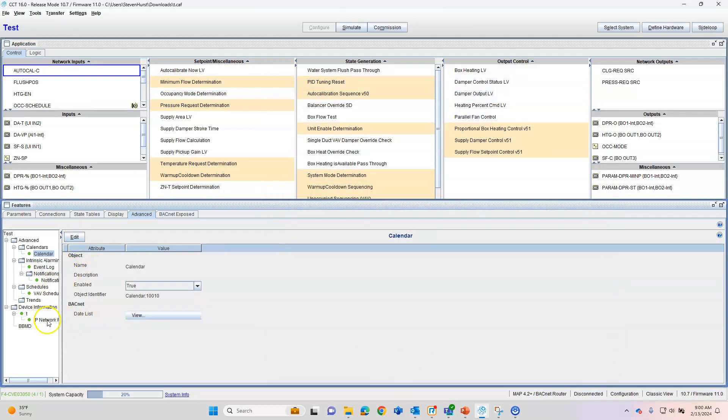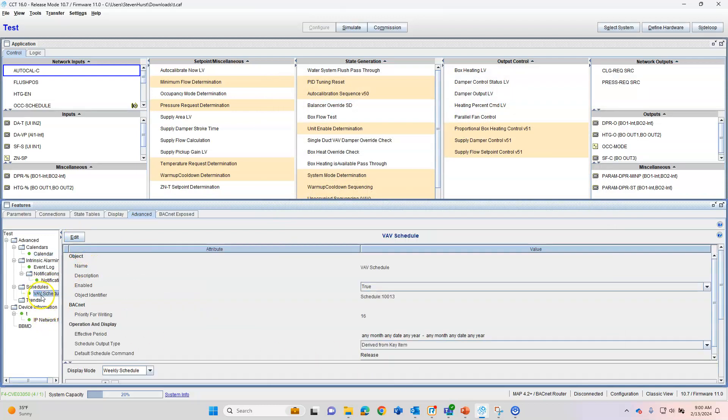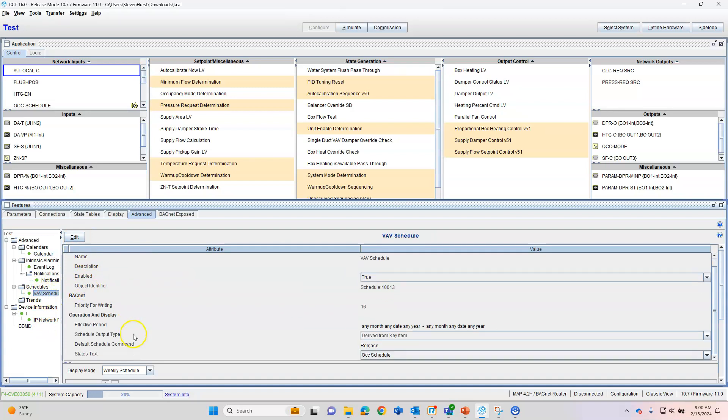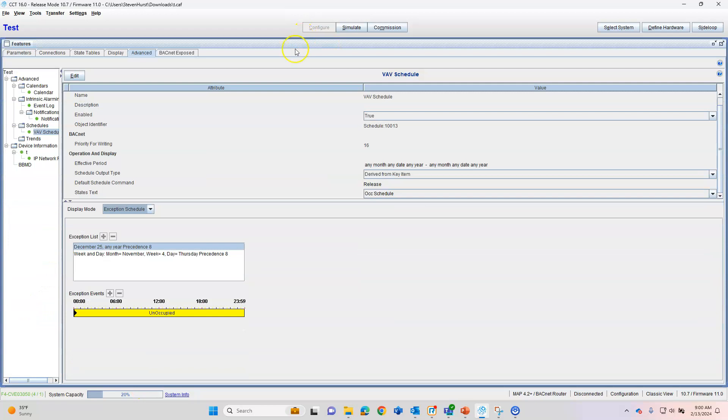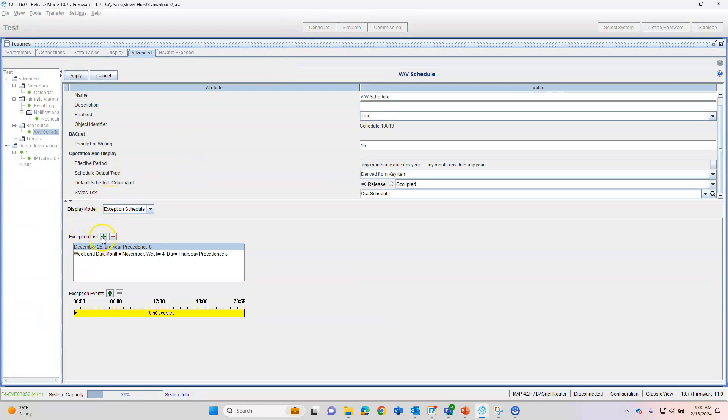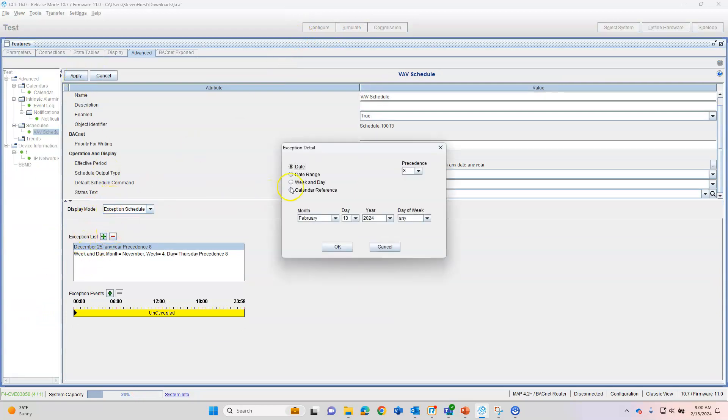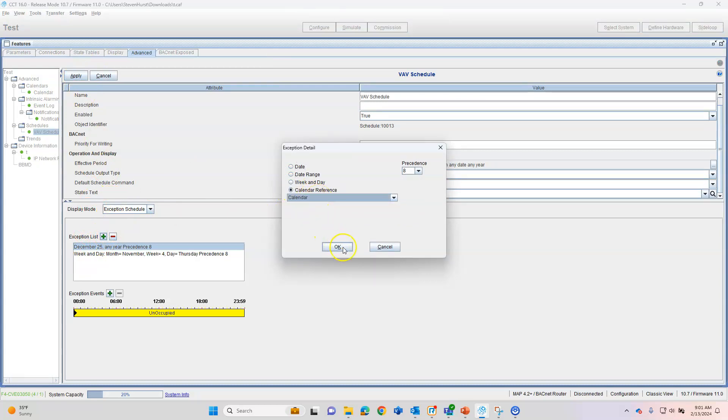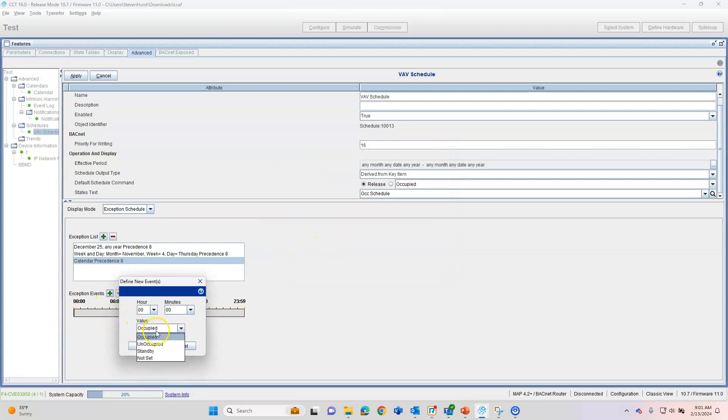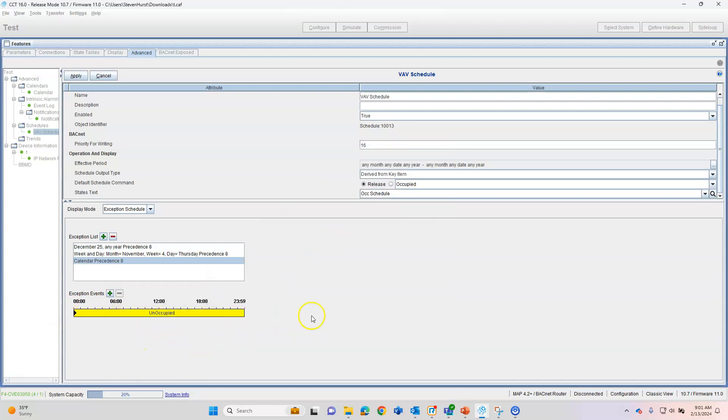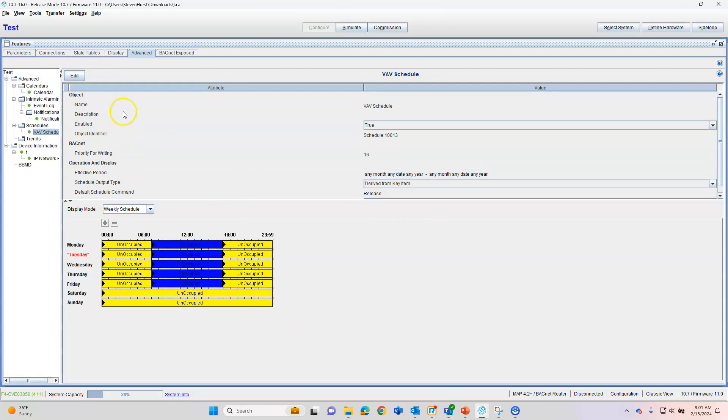Now we can apply and we can go back down to our schedule, exception schedule, edit, new calendar reference. Calendar, okay. Obviously, we want this unoccupied. So now all the dates that we did in that calendar are going to be unoccupied. We're going to apply.